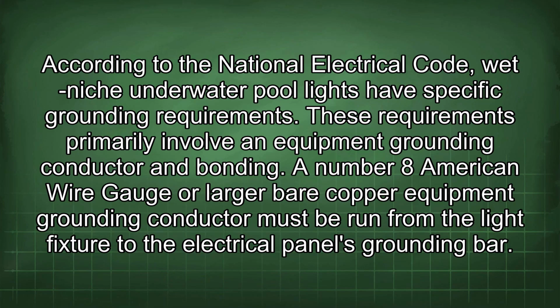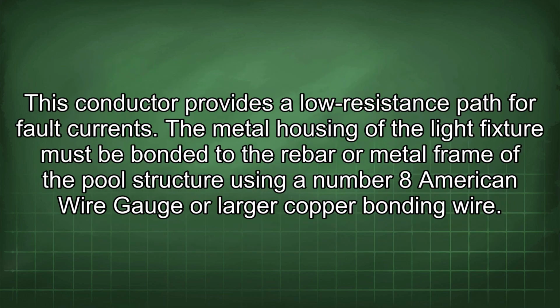According to the National Electrical Code, wet niche underwater pool lights have specific grounding requirements. These requirements primarily involve an equipment grounding conductor and bonding. A number 8 American wire gauge or larger bare copper equipment grounding conductor must be run from the light fixture to the electrical panel's grounding bar. This conductor provides a low resistance path for fault currents.